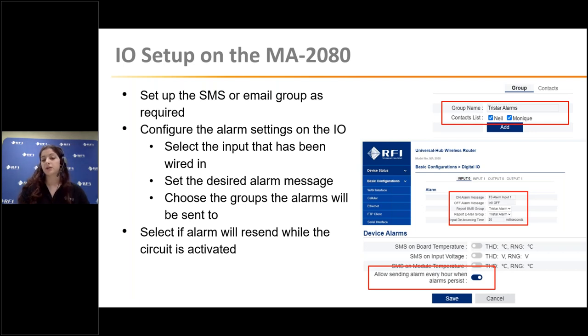We're also able to change the debounce time if needed, but that shouldn't be an issue for the relay drivers. The other feature we have is basically an alarm reminder for the duration that relay is triggered, so every hour we can choose whether a new message is sent out. This ensures it's attended to if it hasn't been, or you can turn that off if you don't want persistent messages. It's a really easy setup, a little extra thing that can make your system more stable and more useful, and it can make those alarms more useful for interpretation by people.